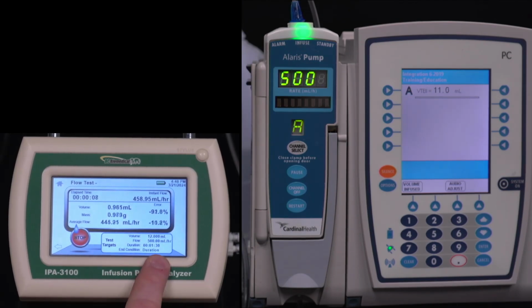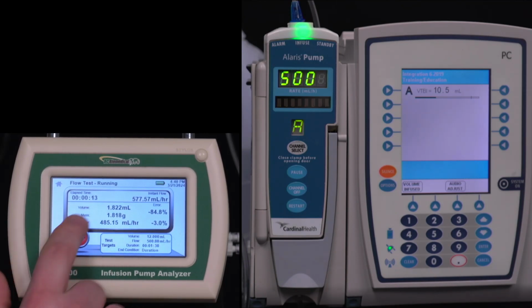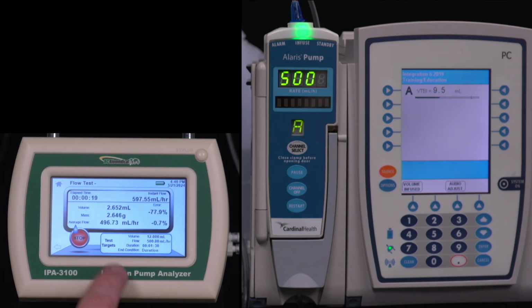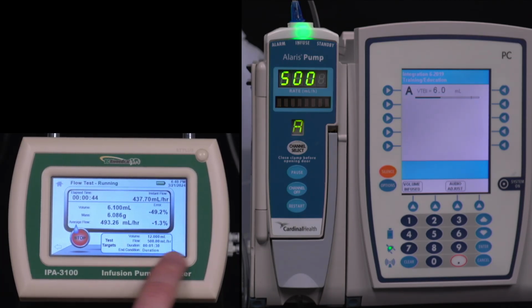So we can see on the screen here, it's showing the measured volume. It's also converting that to grams based on the density that we set, and the density is based on temperature. Online, typically, everybody uses 1 for density. But you can get as accurate as, I think, 5 digits in there. So if you want the official density for your water based on your temperature, you can enter that in. We'll give you the grams right here based on the density that you have set. We can see the settings for the test down at the bottom, so it tells me what I had configured.